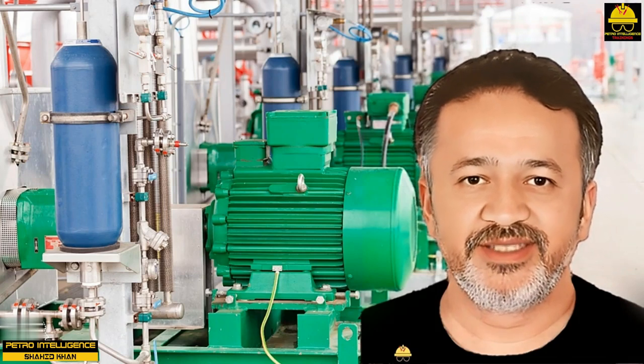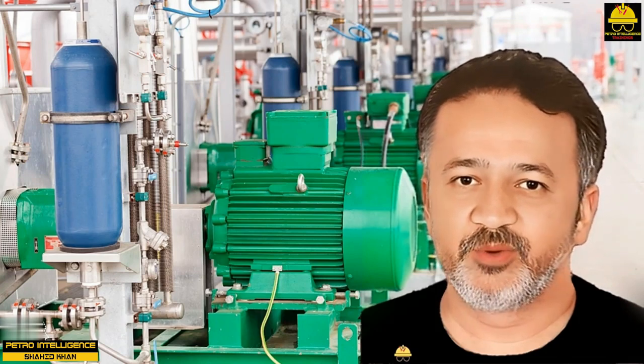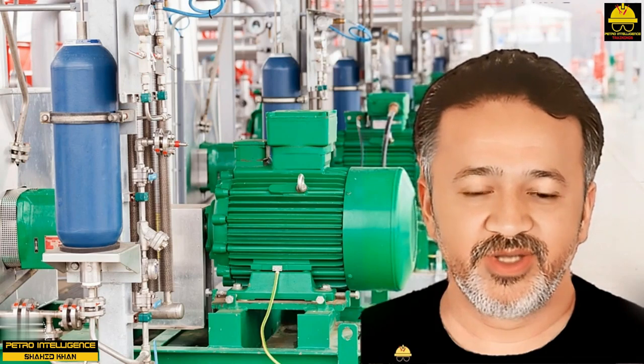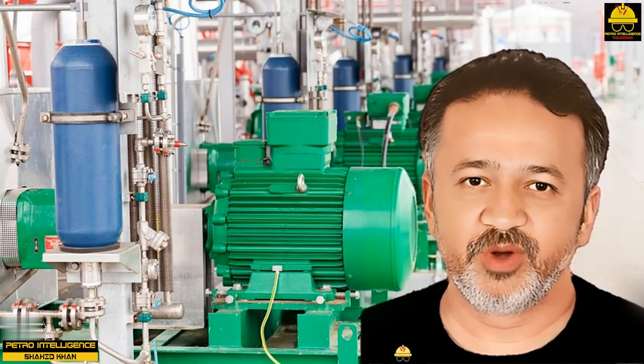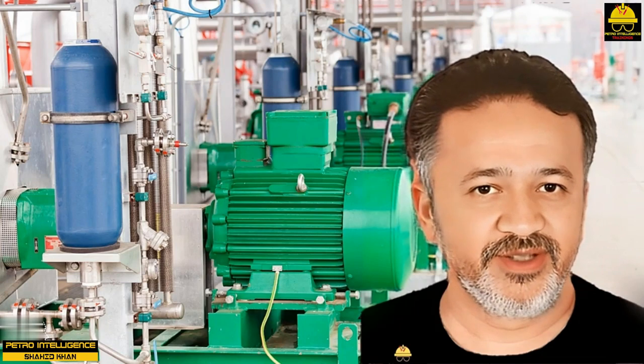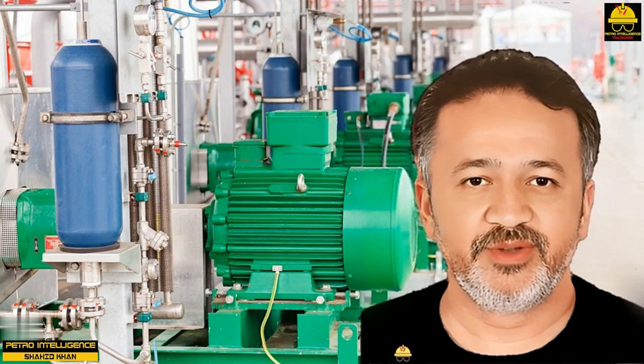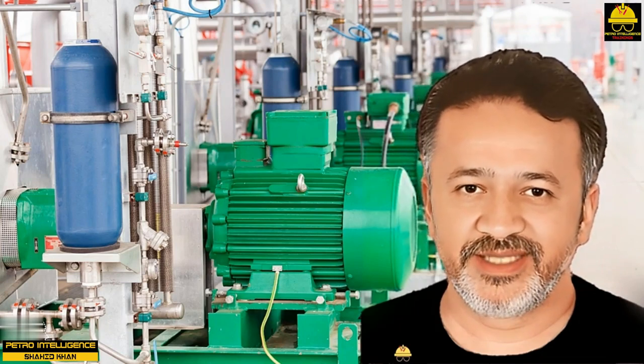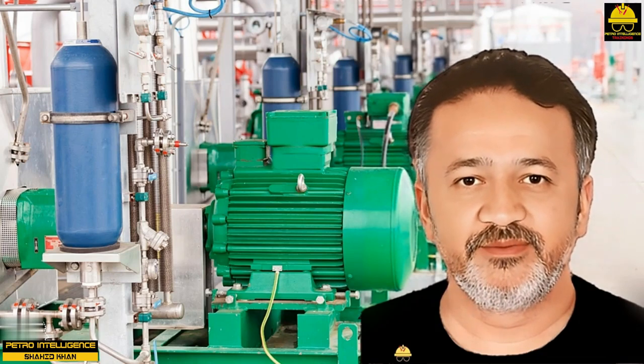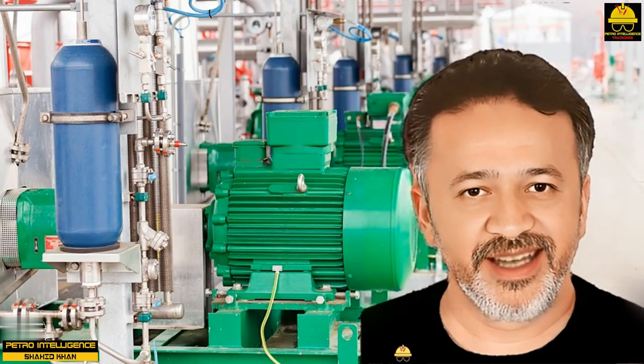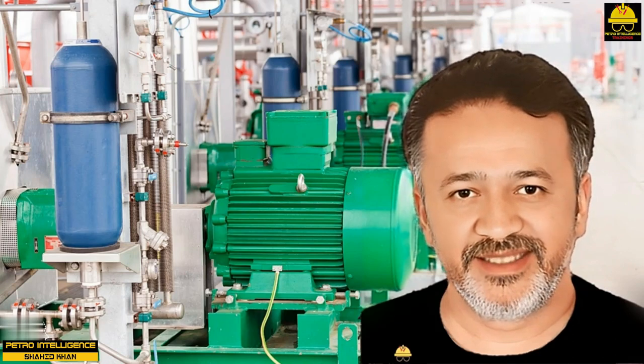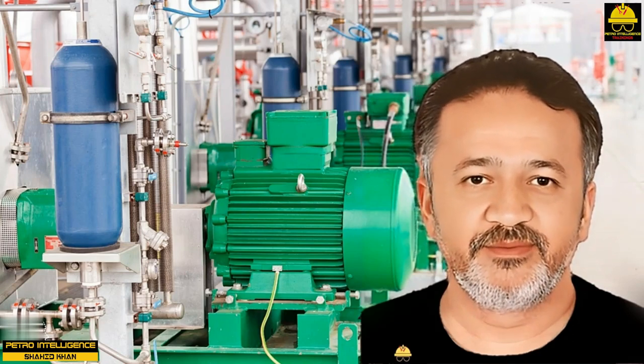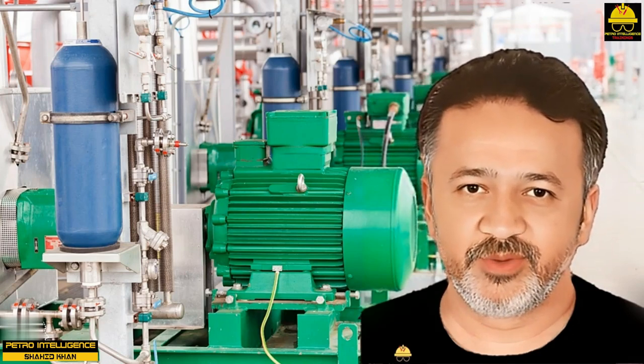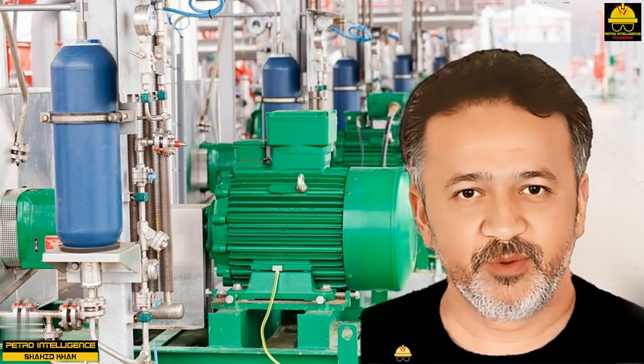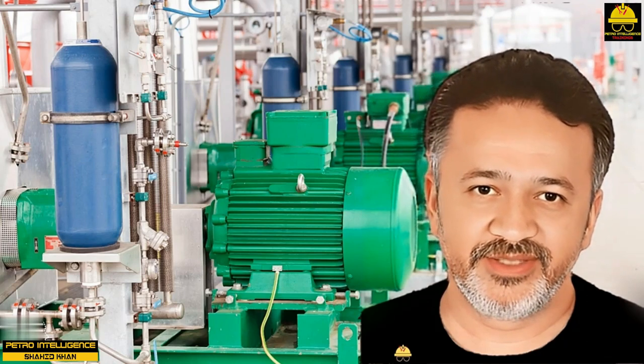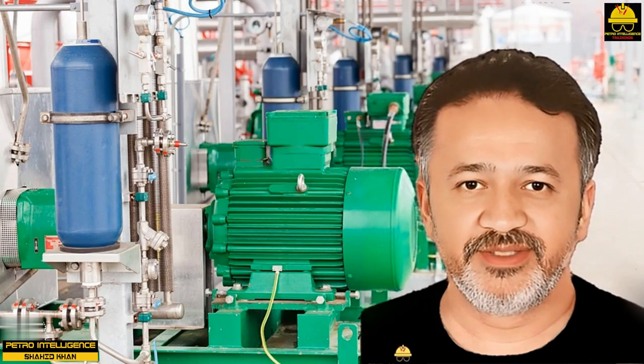During operation, a centrifugal pump will artificially create a low pressure area in the suction eye. If the suction pressure is not carefully controlled, the low pressure could cause the liquid to boil. Boiling creates the condition called cavitation. Net positive suction head, NPSH, usually is calculated in feet of liquid. For example, if a pump took suction off the bottom of a 20-foot open tank with a liquid level of 10 feet, the static head would be 10 feet.